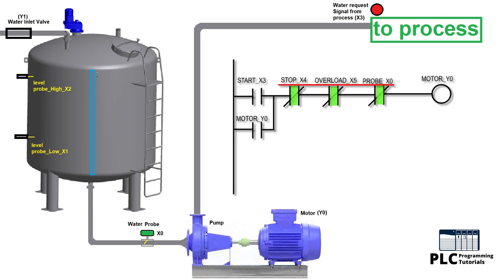As we press the start push button, it will close the x3 contact and motor y0 turns on. Because we are using normal open contact y0 of the motor in parallel with the start push button x3, it will cause motor y0 to get latched on.